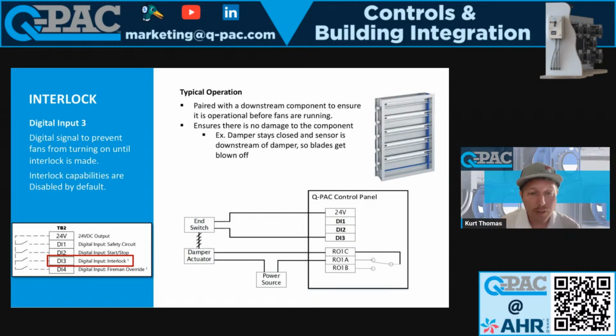With RO1, which is the ready operational relay we talked about earlier, if everything's ready, we get a start signal, your building automation system's calling for air, then we will provide power through RO1C and RO1A, right? We'll provide power to your damper actuator. And then once your dampers are fully open, which may take 5 seconds, may take 60 seconds, some dampers operate at different speeds, then the end switch will be made and it'll close the circuit between 24V and DI3. When that happens, then our fans will actually start to spin.